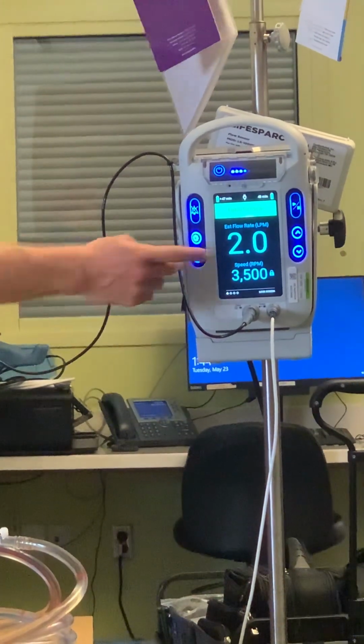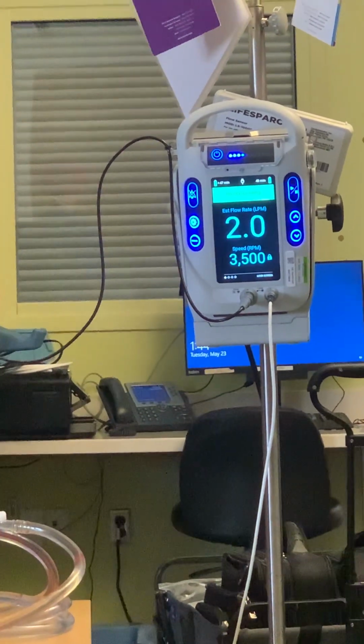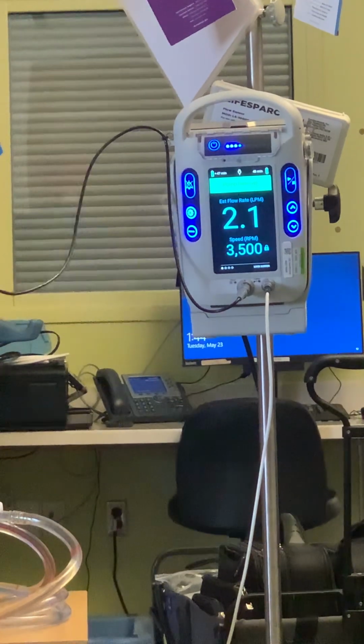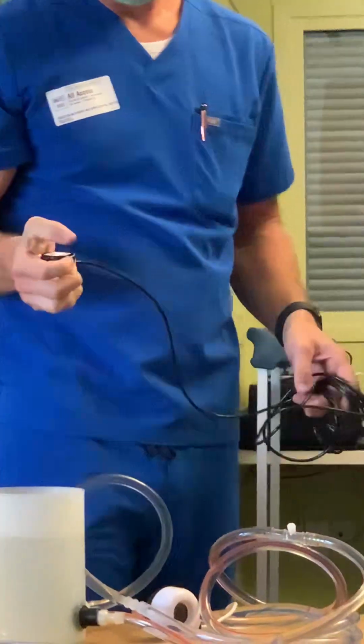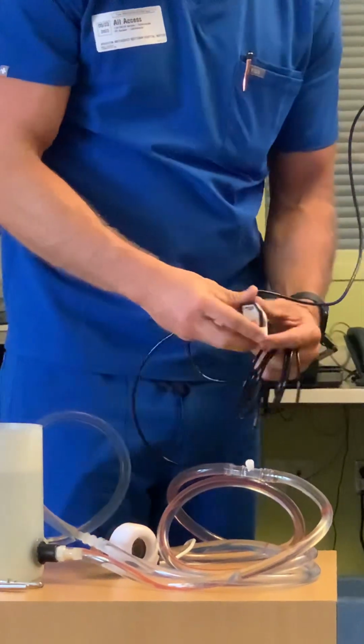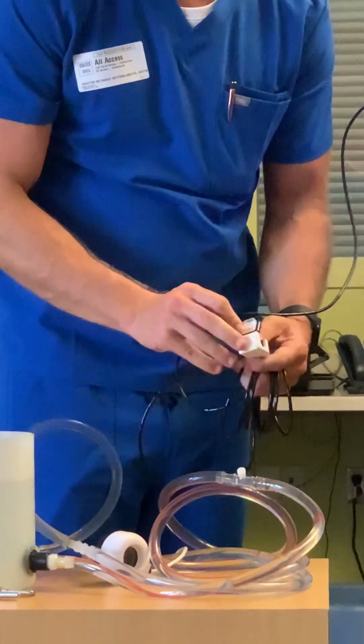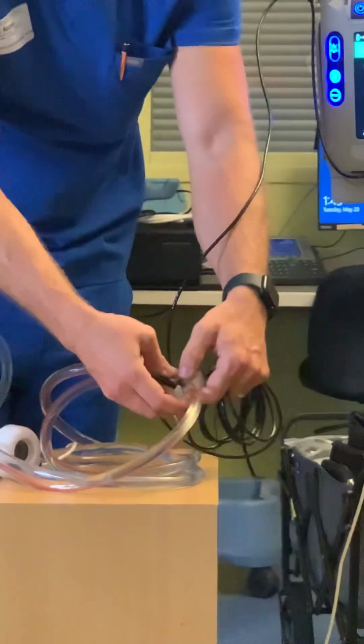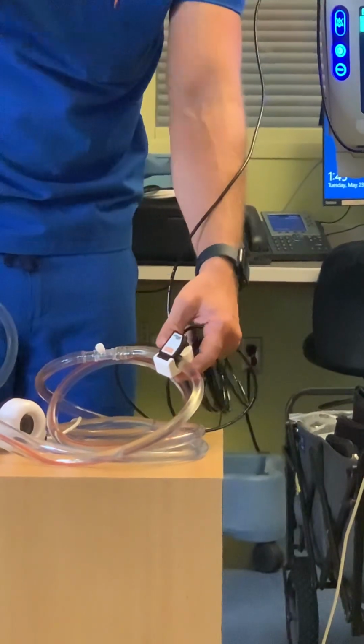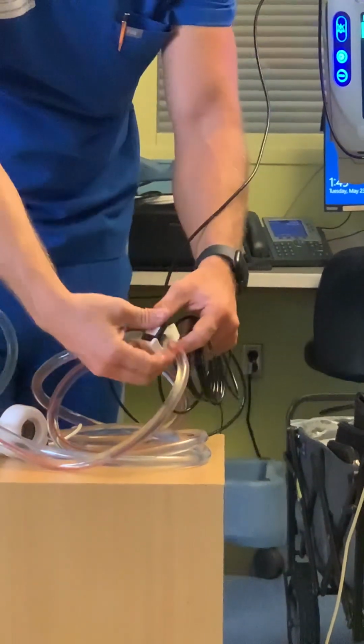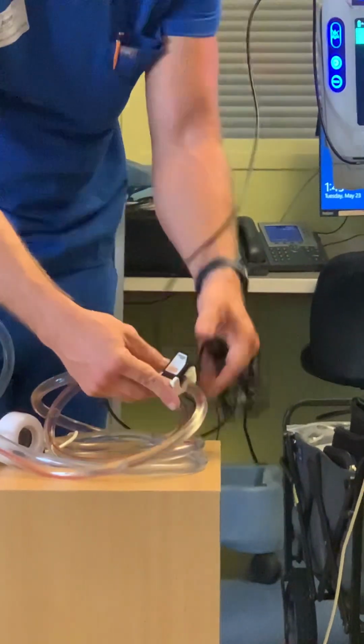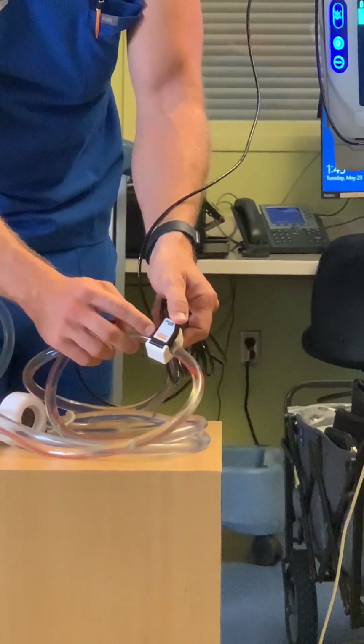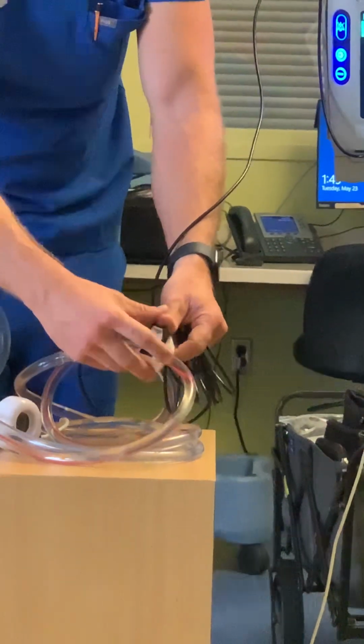So it is estimating flow based off of what it's reading from the pump. This is going to give it a much more accurate description. So we're going to put this wherever it's going to be returning closest to the patient. So in this, there's no oxygenator, so if there was an oxygenator, you would go after the oxygenator, not before it, because it's another resistance in the line. It is unidirectional, so you want to put it in the way that it's flowing.